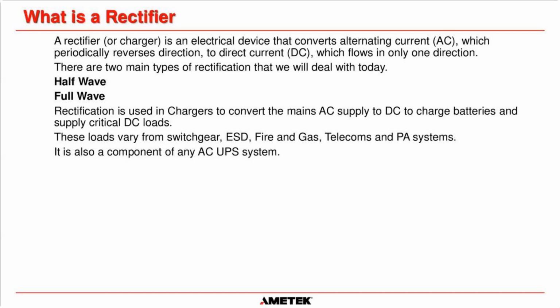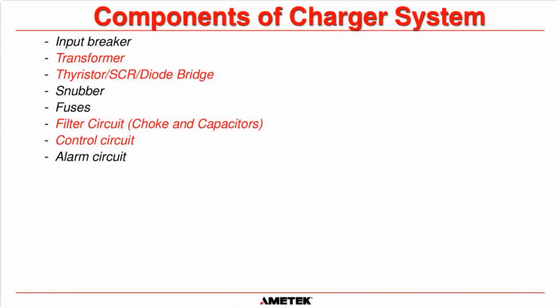Rectification is used in chargers to convert AC to DC, to charge batteries and to supply DC loads. Those loads can be switchgear systems, emergency shutdown systems, fire and gas, telecoms, PA systems, DC lube oil pumps, and numerous other things. It can also be a component of any AC UPS system. If you have a full AC UPS system, the AC has to be converted to DC, and then that DC gets converted back to AC. Hopefully everybody's following along.